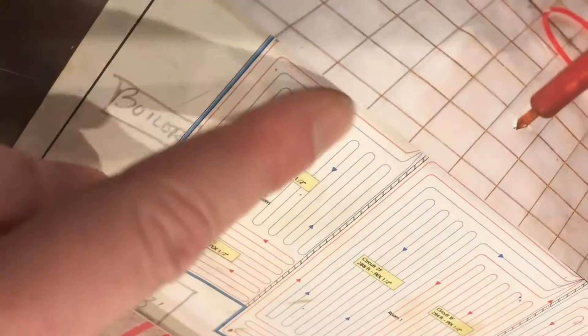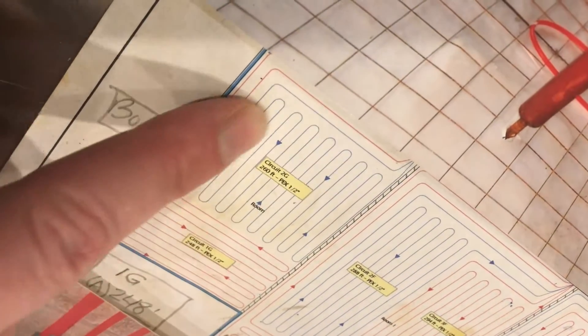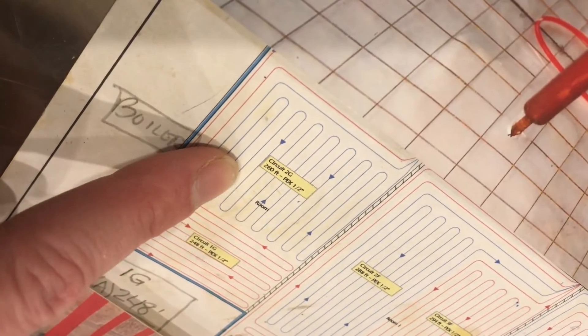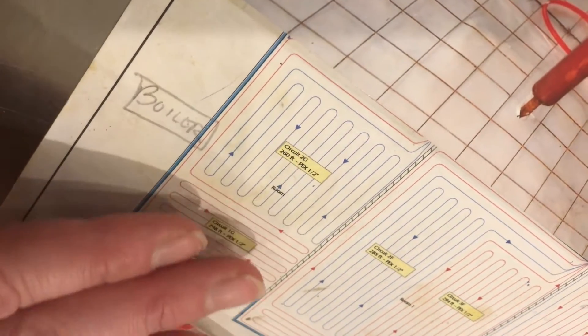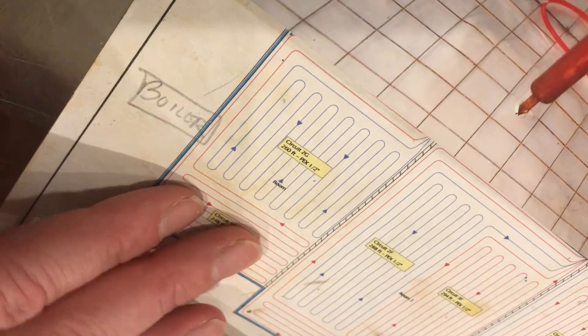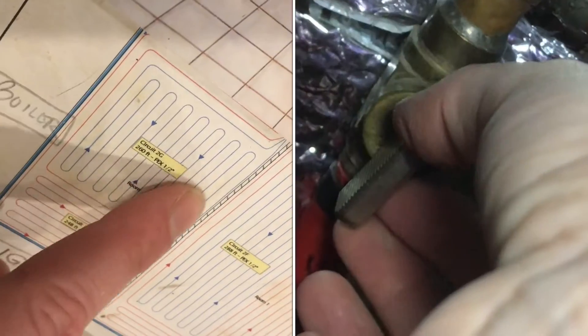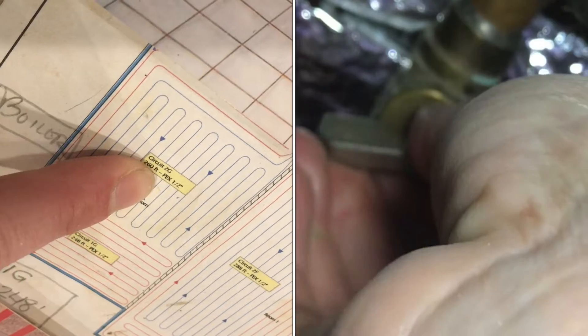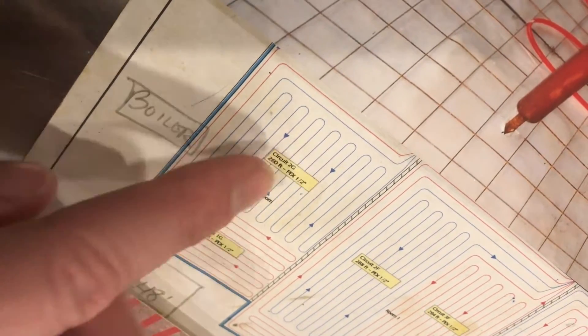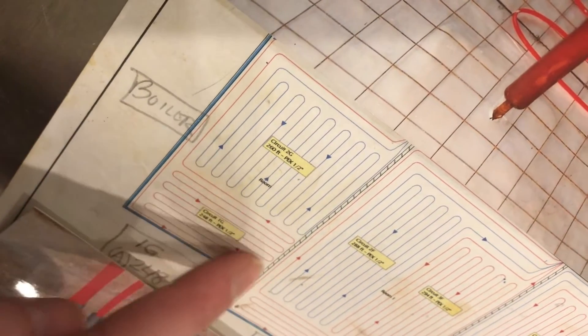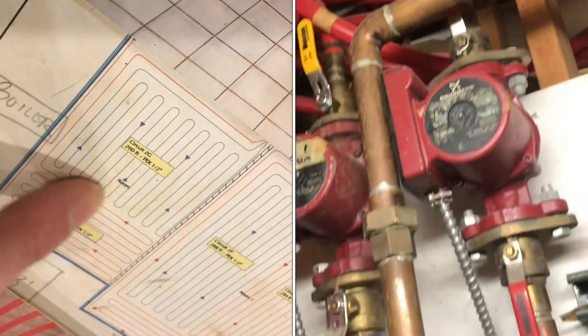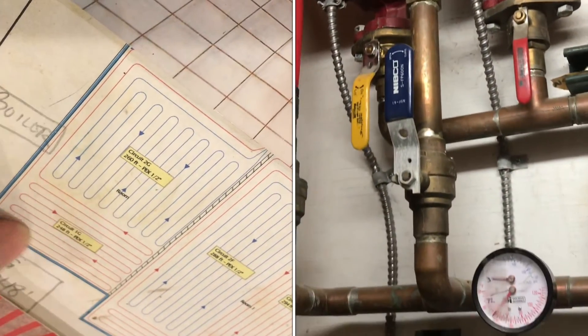So we have found, for example, that in this back room there is very little loss of heat and it tends to get almost hot back there compared to the front room. And so we can effectively turn off this entire loop, not have any water going through these tubes at all, and the entire slab is going to stay warm because all of the hot water will be pumped into the slab but only in this area.